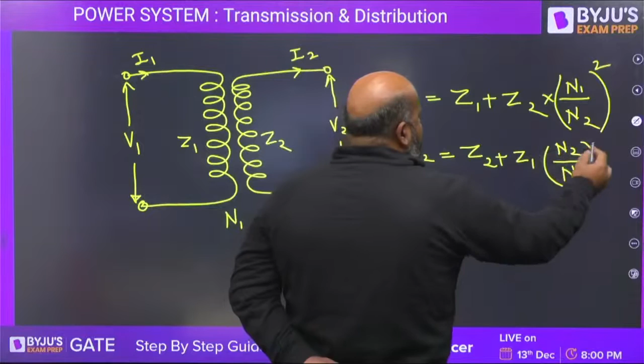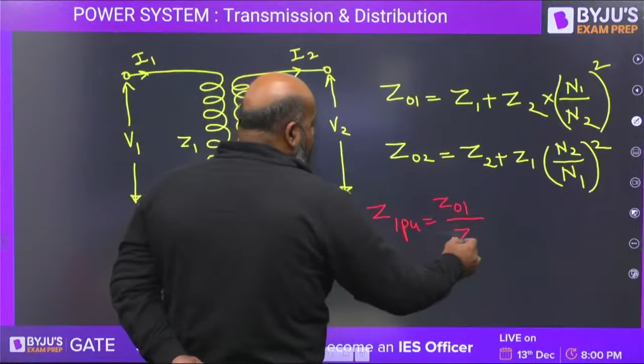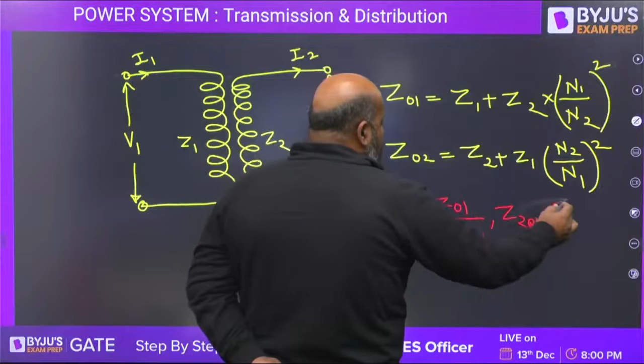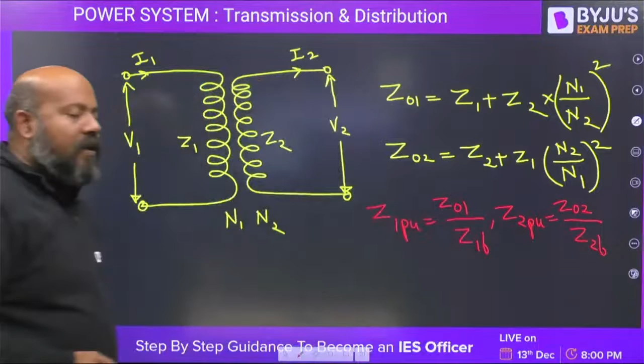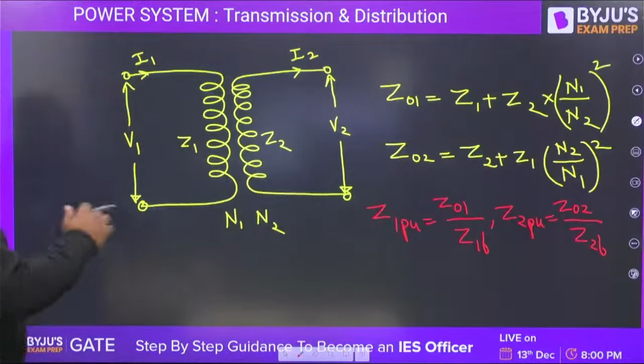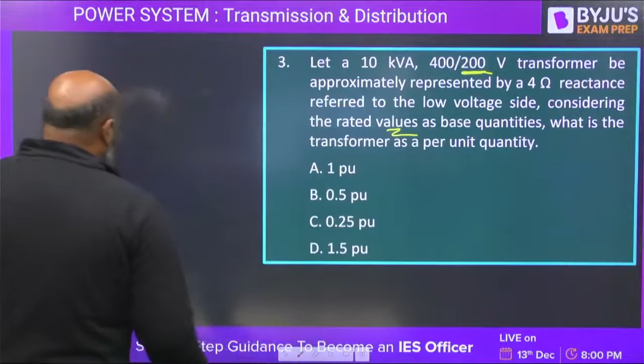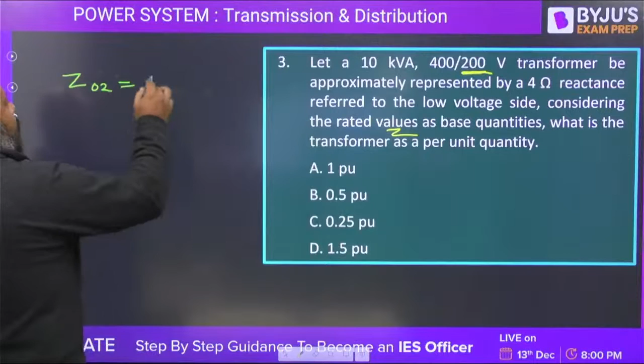Now, if you want to find the per unit impedance, whether you find it from the primary side, it is going to be Z01 upon Z1 base, or if you find it from the secondary side, it is going to be Z02 divided by Z2 base. You know that in per unit, the primary or the secondary per unit impedance of the transformer is the same. In the question, he is giving you the low voltage side. Basically, he is giving you this value, that is Z02, because secondary side is low voltage side. So Z02 is approximately represented as 4 ohms.